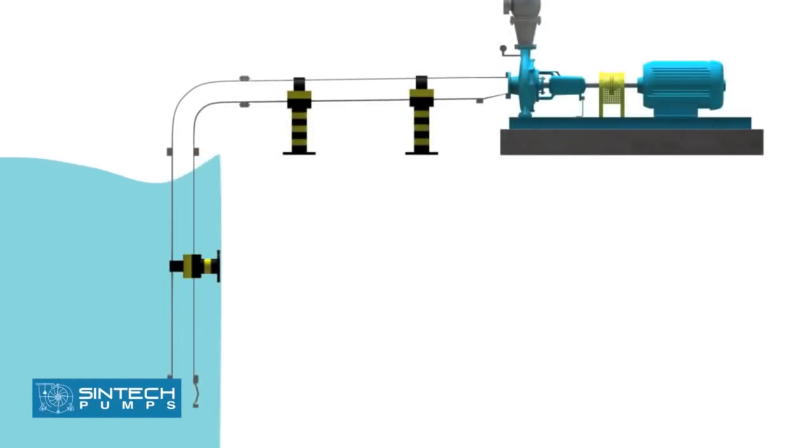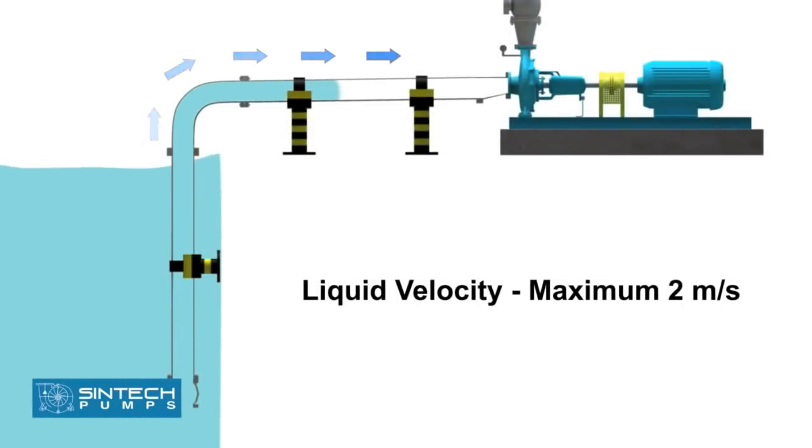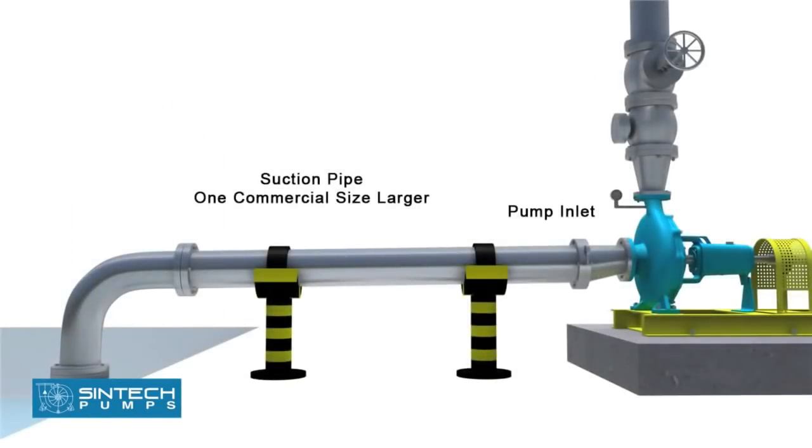The suction pipe should be sized to ensure the liquid velocity of not more than two meters per second. The suction pipe size should be at least one commercial size larger than the opening of the pump inlet.